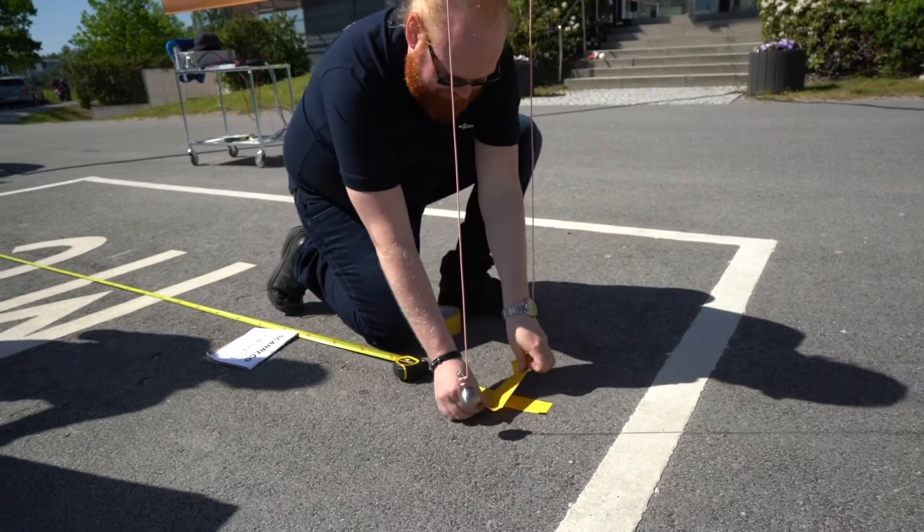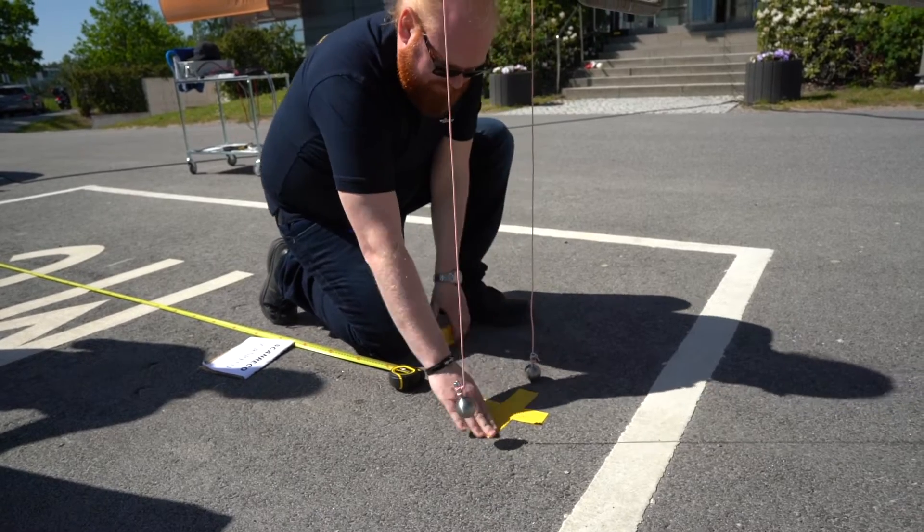In our in-house mechanical lab at ScanRico, we are testing our products for random and sinus vibrations, mechanical shocks and drops according to the IEC 60068 series of standards. We also do some accelerated life cycle tests according to the ScanRico test cycles.